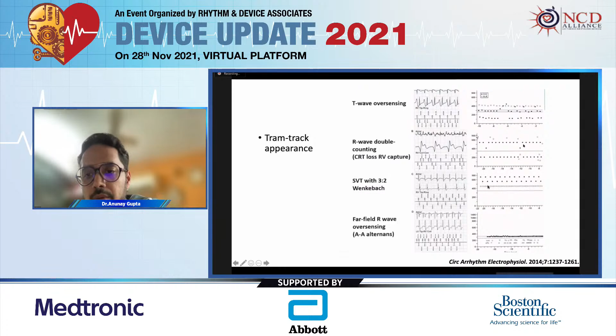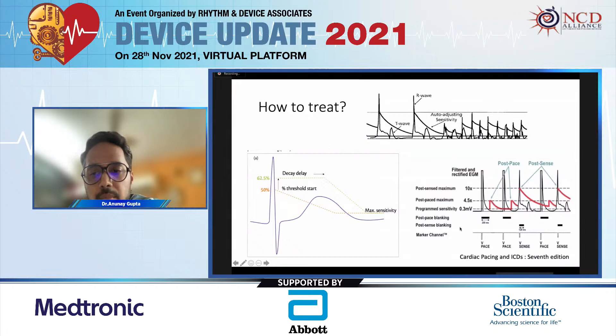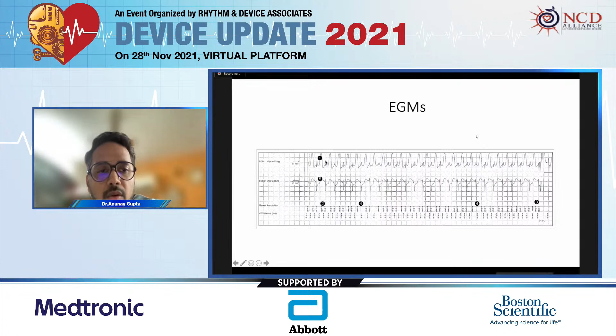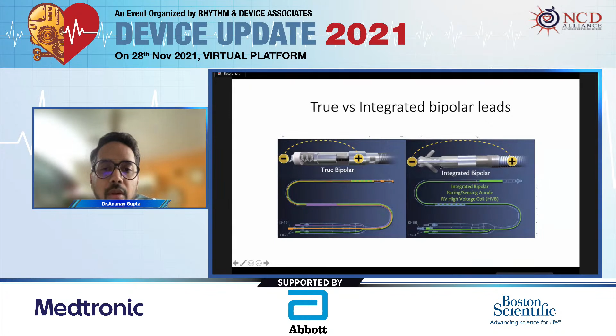So this can be treated, as I've told, with the auto adjusting of sensitivity which happens in the device; you can delay the decay, and even the threshold start rate can be increased. And in this case, you can see that this T-wave is not oversensed in the V tip to high voltage coil, it's only being sensed on V tip to V ring. So if we change from a dedicated true bipolar to an integrated bipolar, we can avoid the T-wave oversensing.